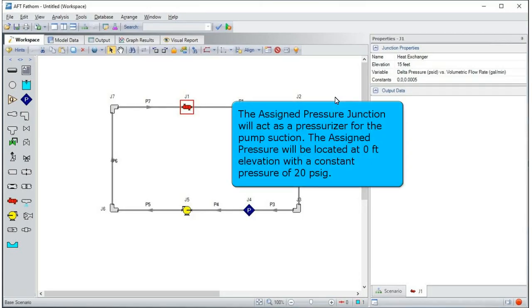The assigned pressure junction will act as a pressurizer for the pump suction. The assigned pressure will be located at zero feet elevation, with a constant pressure of 20 psi gauge.